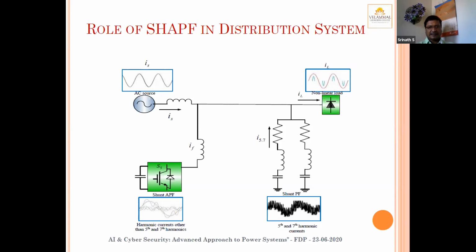The nonlinear load injects harmonics into the system, and the shunt active power filter starts filtering it out. Actually, the shunt active power filter is basically an inverter connected to a separate DC source, connected in parallel to the system. And in order to eliminate selective harmonics, we have also connected a shunt passive filter into the system.